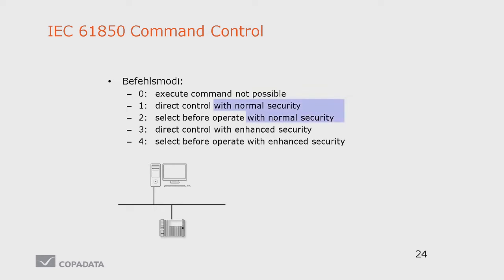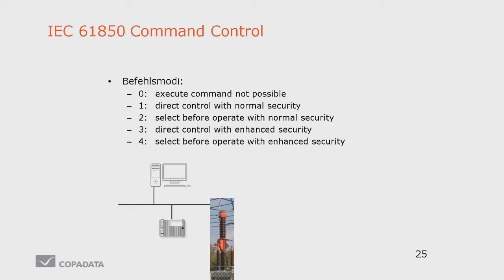And what is it about normal security and enhanced security? Normal security means that I just speak with the server. The enhanced security means I speak first with the server, I get the confirmation, and when the server finds out the real switchgear has changed its position, I get the termination. So this is the difference between normal security and enhanced security.